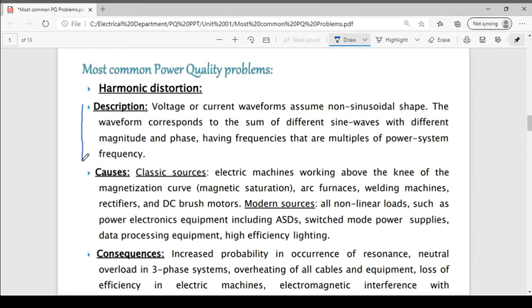So what are the causes? Classical sources are electrical machines working above the knee of the magnetization curve. This is one of the causes, magnetic saturation. Others are arc furnaces, welding machines, rectifiers, and DC brush motors. One more prominent cause behind harmonics is nonlinear load. What is a nonlinear load? A load which does not obey Ohm's law, a load which draws non-linear current from the source. Examples include power electronic equipment, switch mode power supplies, data processing equipment, high frequency lighting, and variable frequency drives, AC drives, and DC drives, which are the most common sources of harmonics.